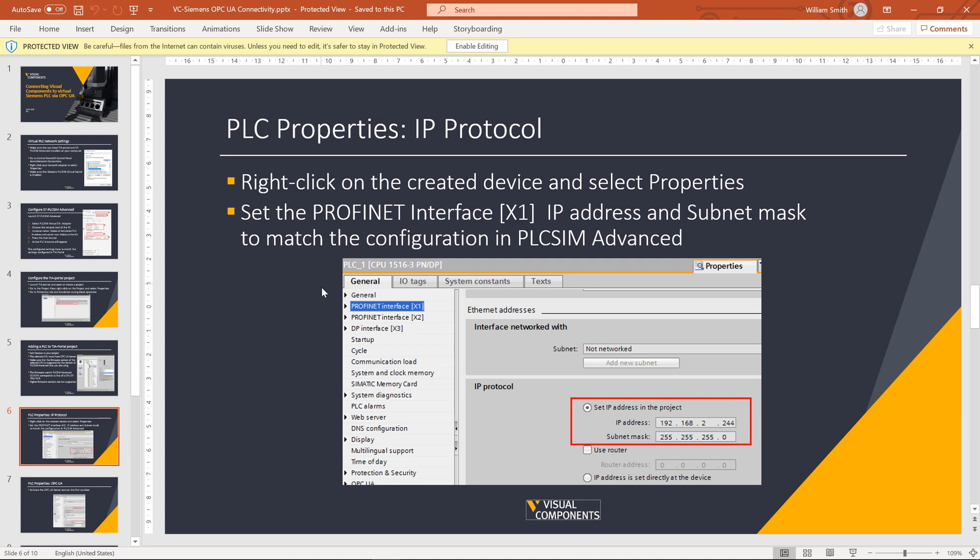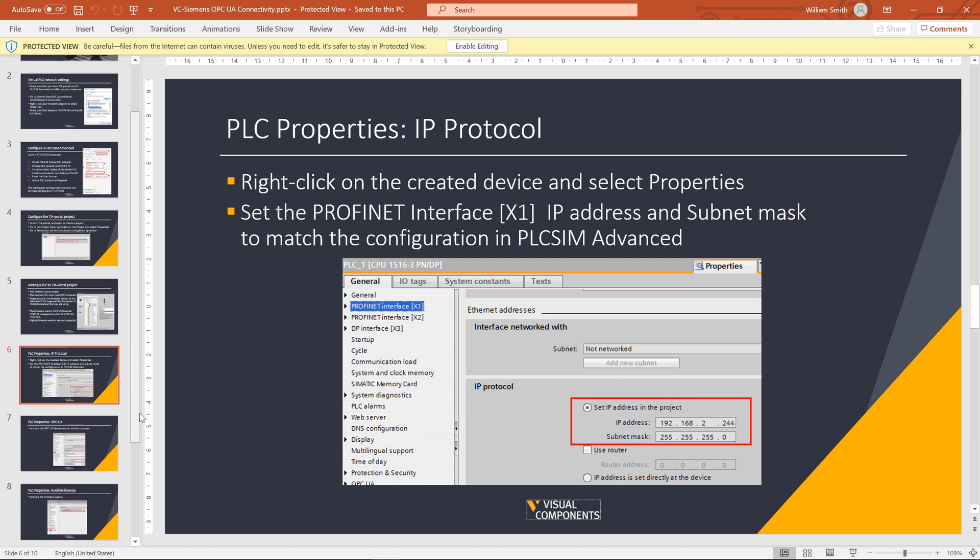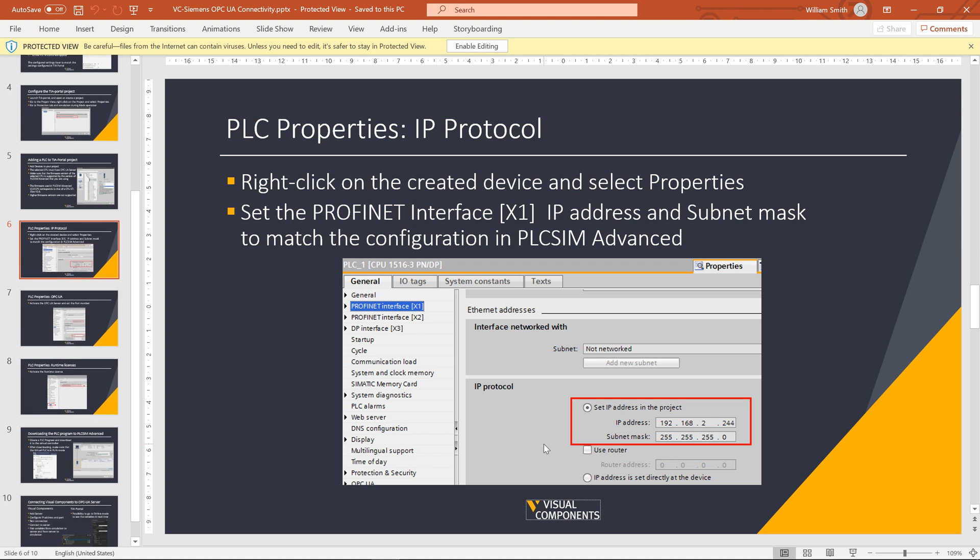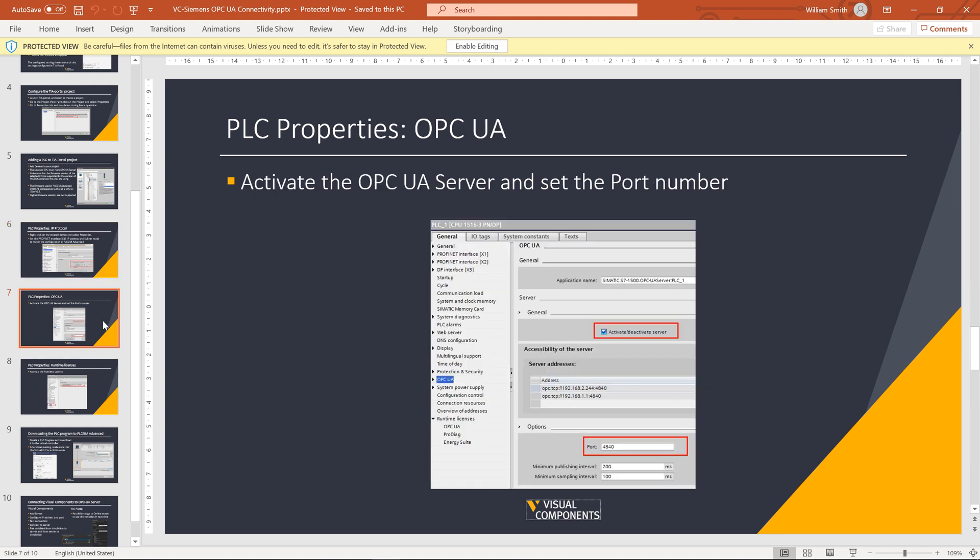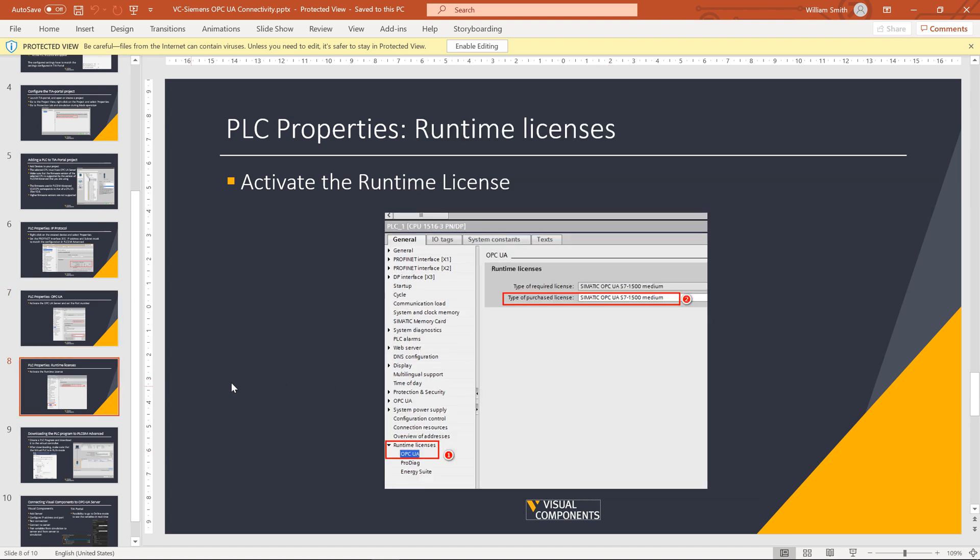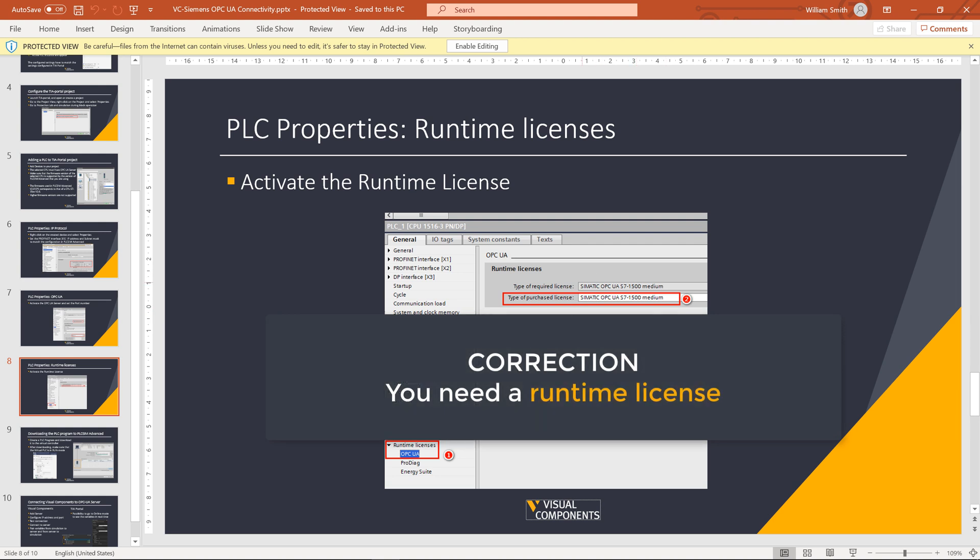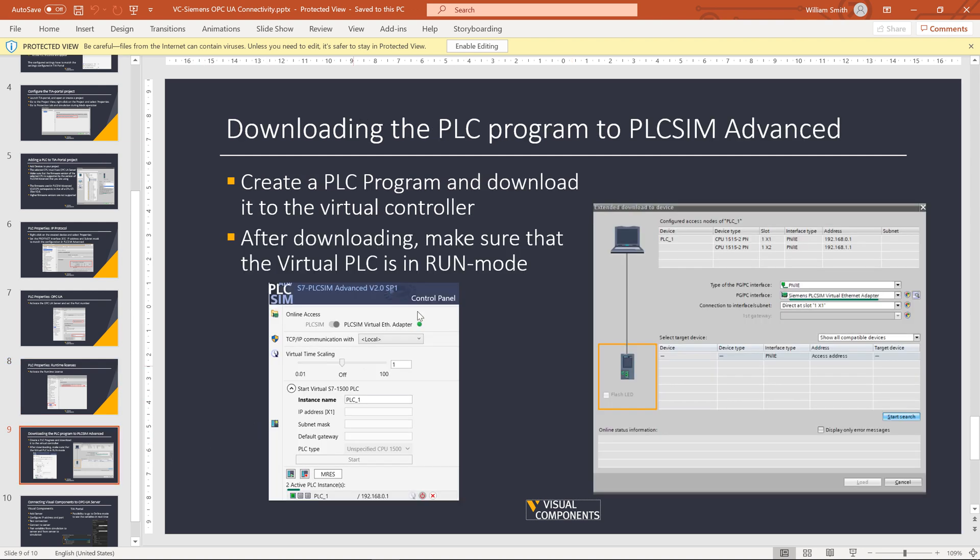For the properties itself, you might want to define that. Right now in my project, I'm using, I believe, the default IP address, so 192.168.0.1. You activate the OPC UA server in your PLC and make sure you have the port number defined. And here's an issue about the certificate I mentioned, so it can be small, medium, or large. It's really easy to get this certificate in TIA Portal.